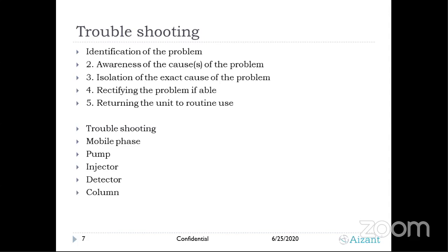Just an example: if you are getting a distorted peak and you do troubleshooting, identify where the root cause exists, and rectify it, then routine operations resume. It means you can start your analysis. Our troubleshooting today, with respect to the basic components of HPLC, will be divided into 5 sections: mostly the mobile phase, the pump, the injector, the detector, followed by the column.